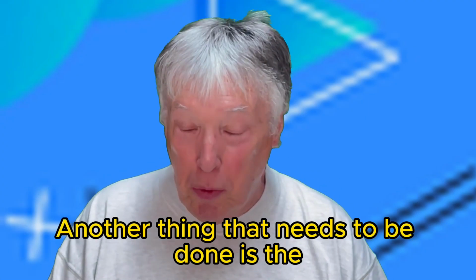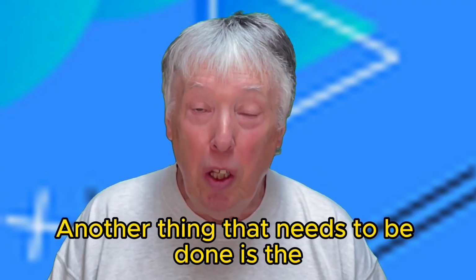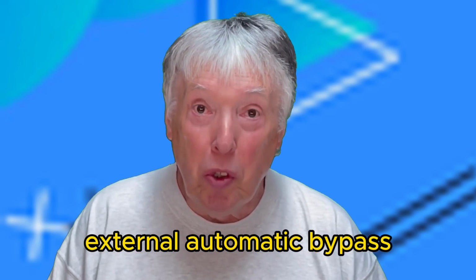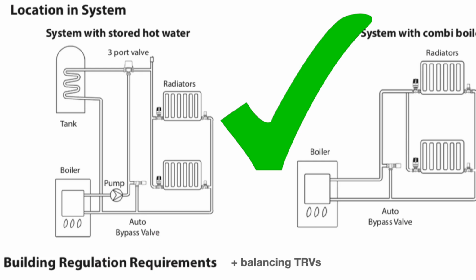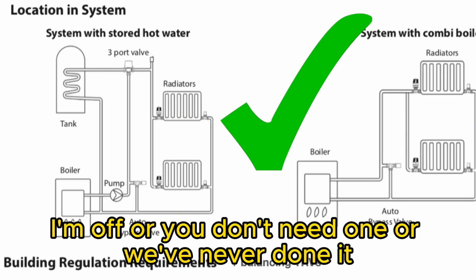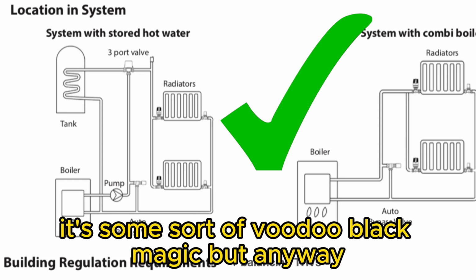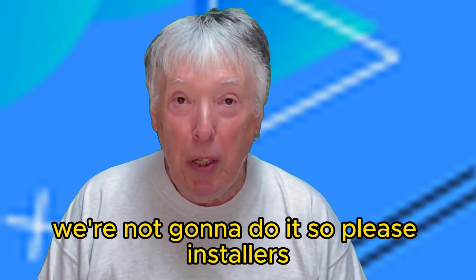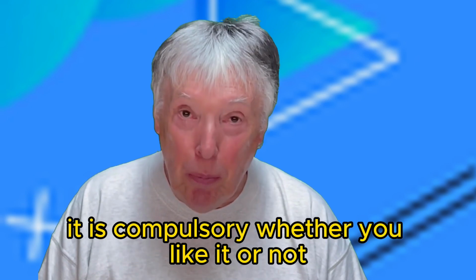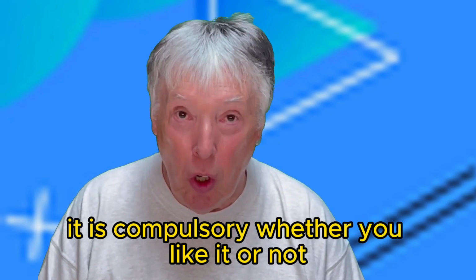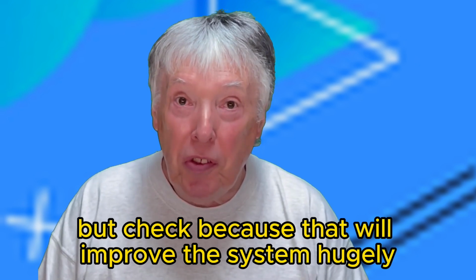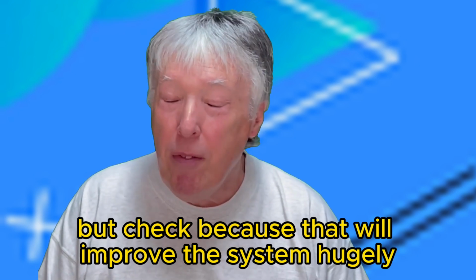Another thing that needs to be done is the external automatic bypass. I don't know why installers say to customers, it's in the boiler, I'm off, or you don't need one, or we've never done it. I don't know what it is. It's some sort of voodoo black magic, but anyway, we're not going to do it. So please, installers, it is compulsory whether you like it or not. But check, because that will improve the system hugely.